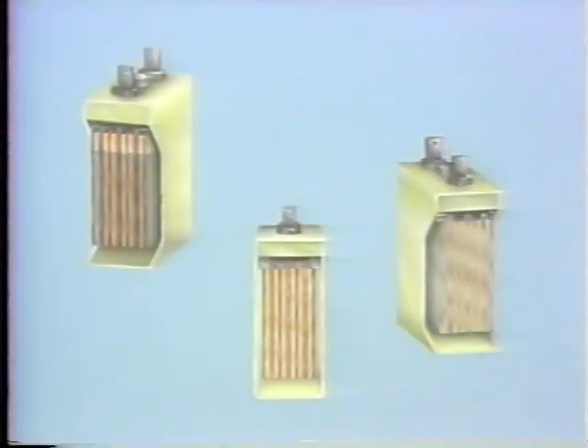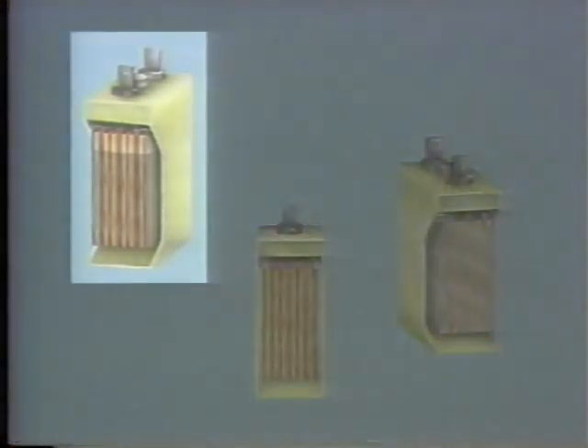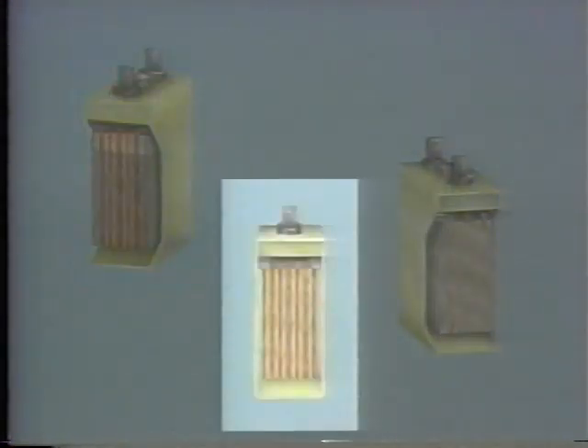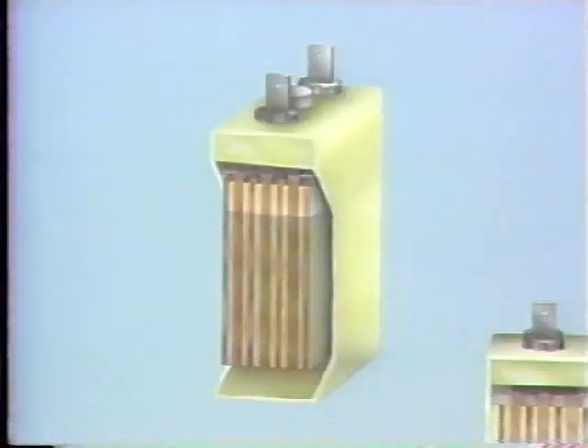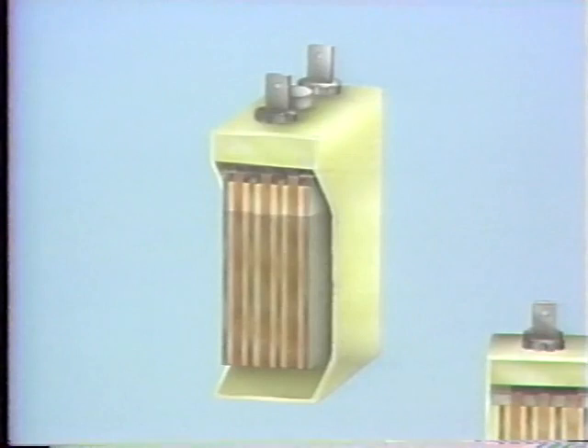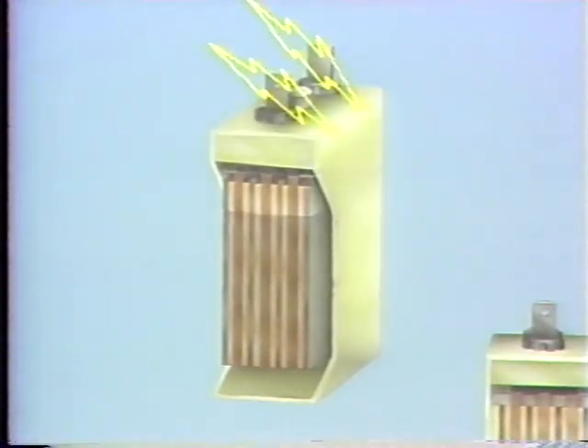Every so often, one cell of a station battery will fail to take a charge. In many cases, the only solution is to replace it with a new cell. The replacement cell may come from the manufacturer in any one of three conditions: wet charged, dry charged, or dry uncharged. A wet charged cell has activated plates of lead and lead peroxide, and it's already been filled with electrolyte by the manufacturer. Before it's installed, all it needs is a slow freshening charge at the finishing rate shown on the cell's nameplate.